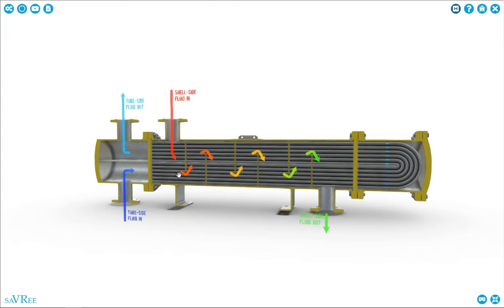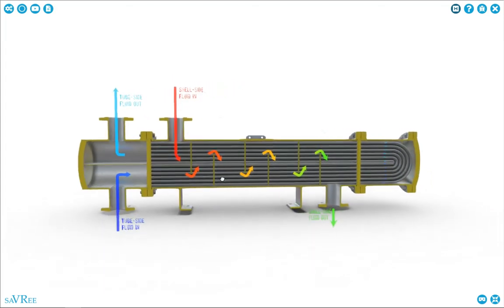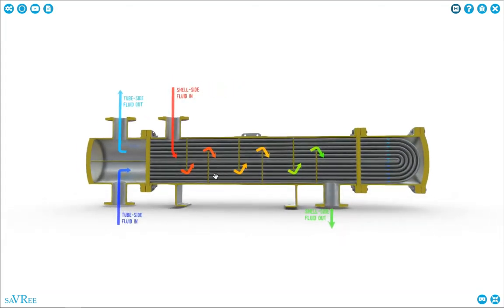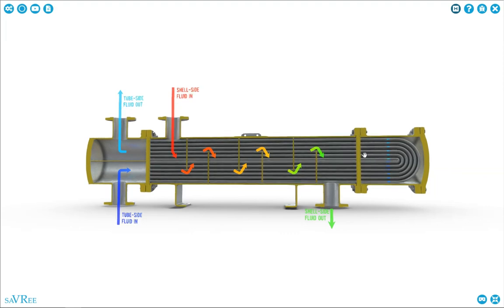So the shell side looks the same. We've got baffles. We've got a pathway through. We have our tube side over here looks the same. So we have an inlet, and we have a cavity here that's isolated from the inlet to the outlet. So everything has to go through these tubes. What's a little different about this one is that it is a U-tube design. So the flow will always stay within one tube, and that tube is then curled around and returns out at the tube side. So this is what we'd call a U-tube-type heat exchanger or shell and tube-type heat exchanger, as opposed to the other one where we don't have that U-tube.